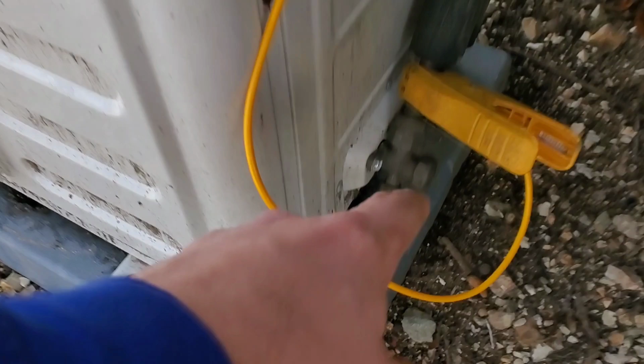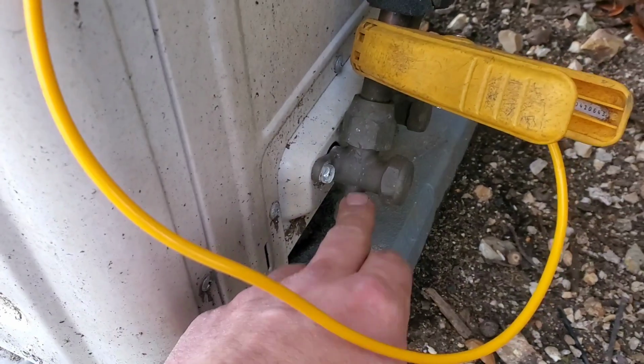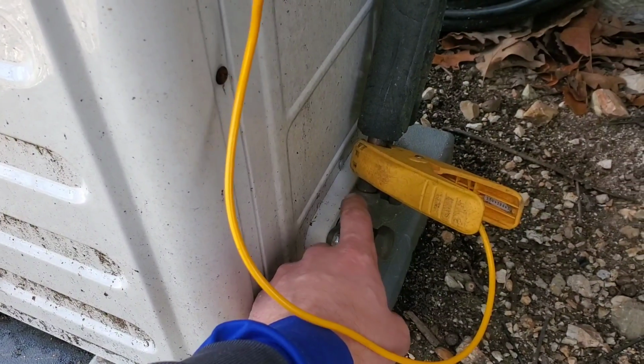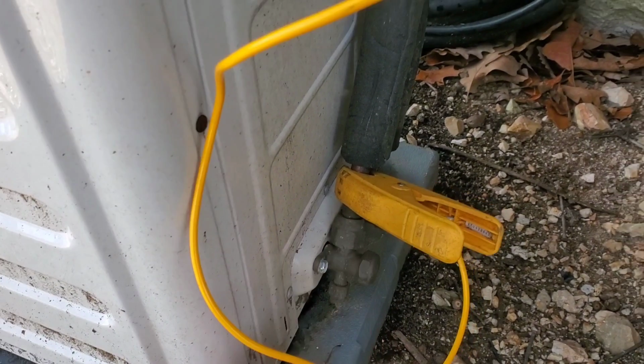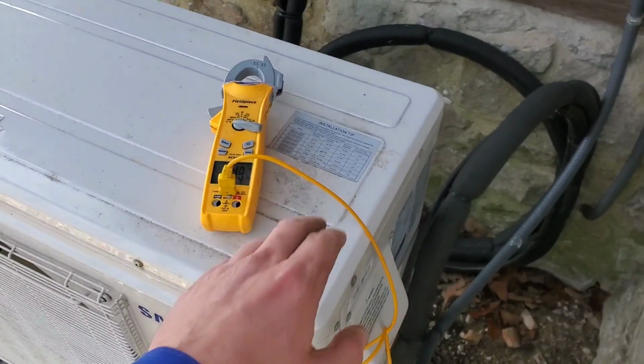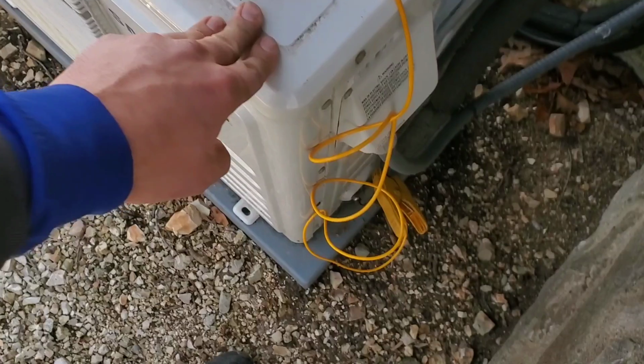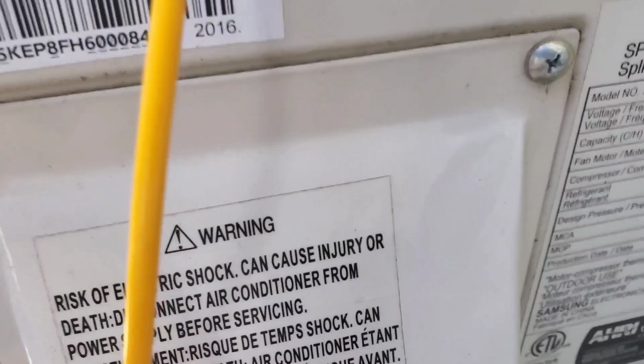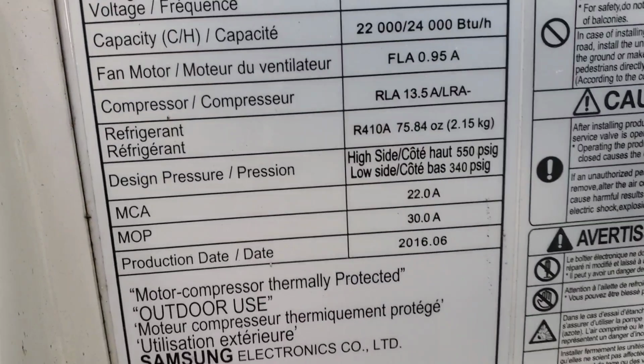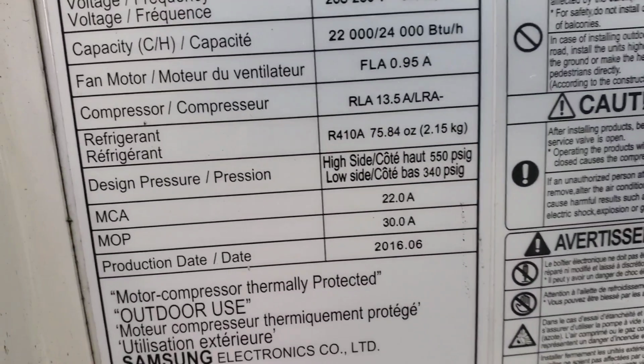vapor line there. So I'll hook my gauge up here and I'll measure this pressure, and I'll want this to be around 350 right now, but it depends on outdoor ambient conditions. Always factory charge these units, always. I'll show you right here. Factory charge is 75 ounces. So 75 ounces is what we're looking at for this unit.